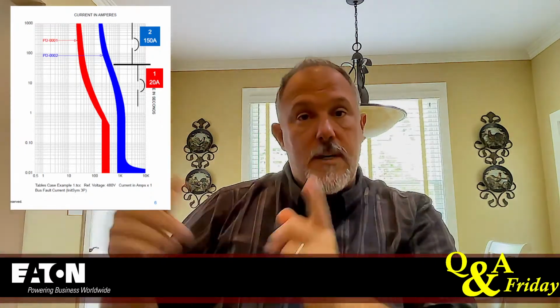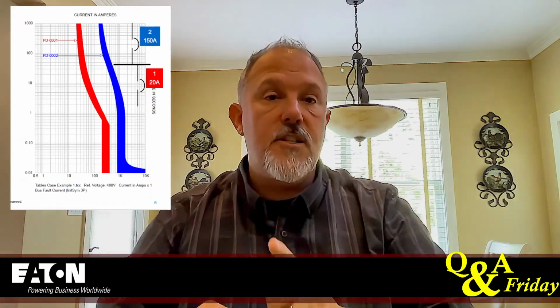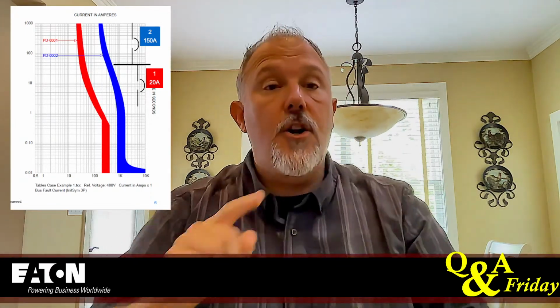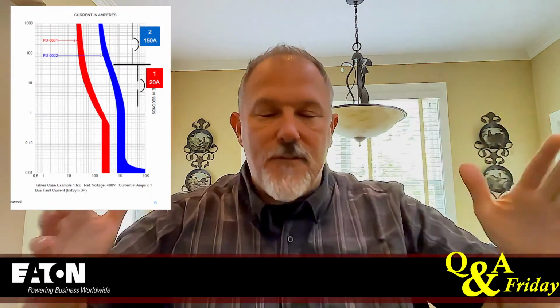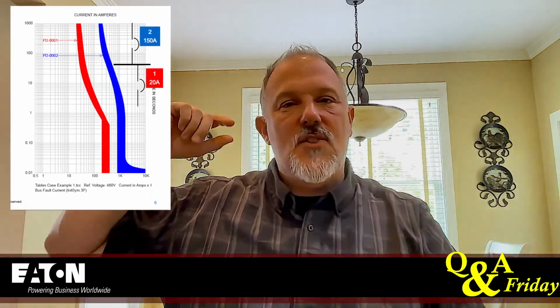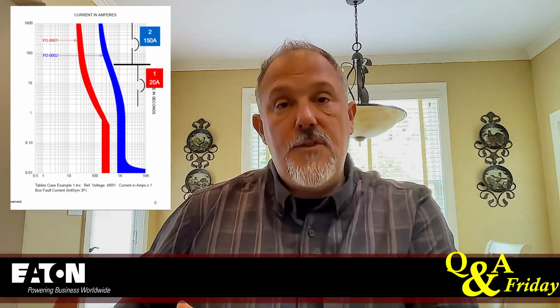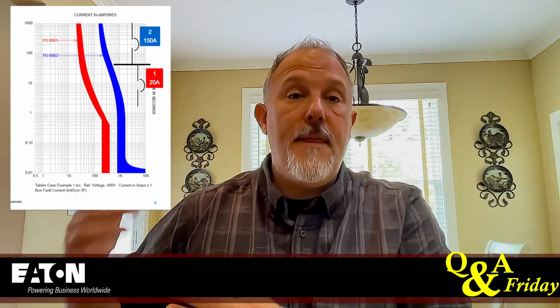So I can address selective coordination by making the upstream device larger. What does that do? It may cause me to increase the conductor size. It may cause me to increase my downstream equipment size. And also, not every circuit breaker fits in every panel board. Right? So I might even have to increase the size of the panel board upstream to accommodate, instead of a 150 amp molded case circuit breaker, maybe a 400 amp frame or an 800 amp frame circuit breaker that's adjusted down. So the new frame I get into might not fit in that upstream panel board.